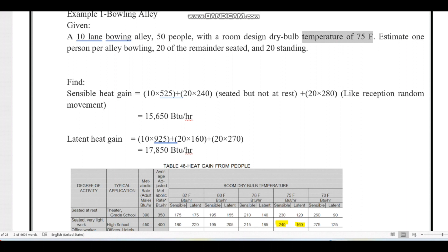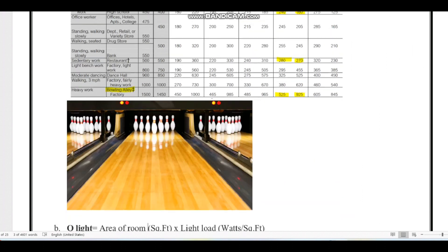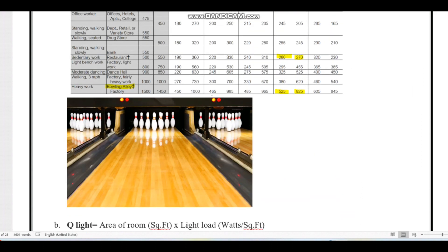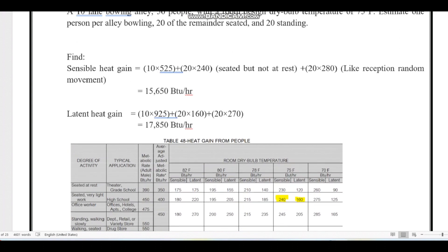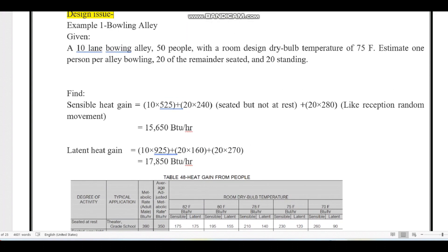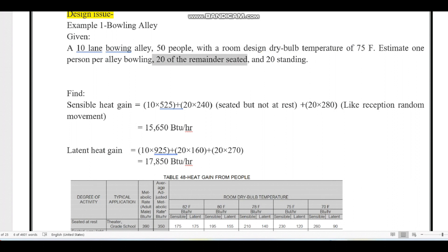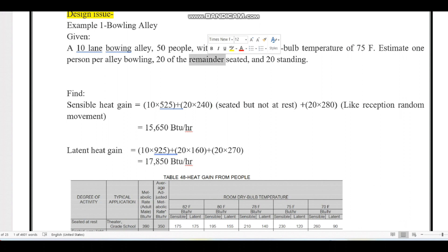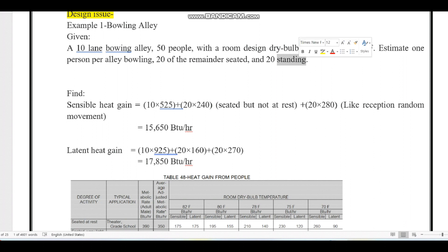As a design example, consider a 10-lane bowling alley with 50 people total, at a room dry bulb temperature of 75°F. One person per lane is playing — 10 people. Twenty people are standing watching the game, and 20 people are seated watching. The activity levels differ: players are doing heavy work, seated viewers are doing very light work, and standing viewers are somewhere in between.